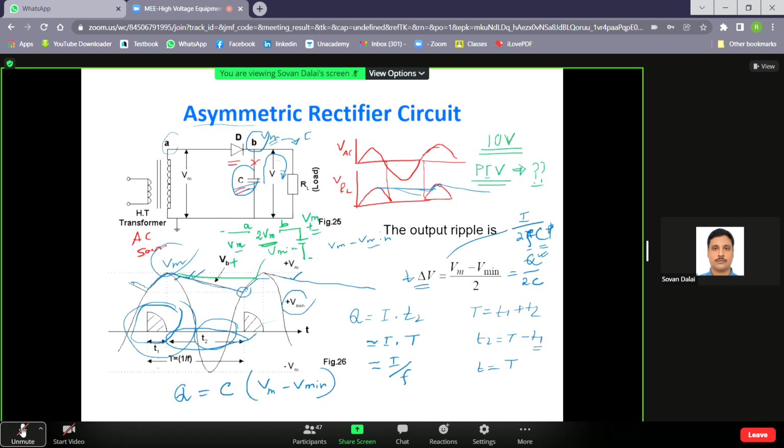Hence, no MMF balance takes place between the primary and secondary. So what will happen? This may cause saturation of the transformer core with the increase of load current. If the core saturates, then you will not get that proper voltage. So special design precautions should be taken in order to avoid core saturation. Either your core cross section should be increased, or you have to select a special transformer.